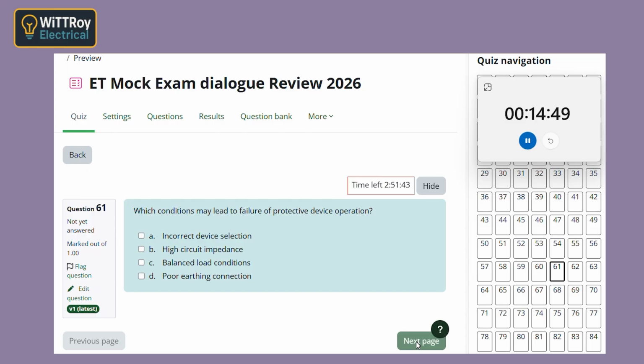Exactly. Poor earthing connection creates the same kind of problem. Fault current path becomes weak or unreliable. And wrong device selection means even if the fault current is there, the device may still not operate as needed. Yes, it may be rated too high or have the wrong characteristic. Balanced load conditions are wrong because balanced normal load does not explain failure of protective device operation.